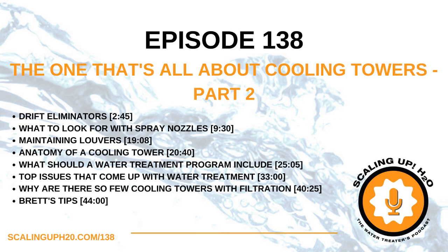So a couple other quick ones. These units, because they have the spray pump and the riser pipe on them, the closed circuit coolers and evaporative condensers, that is, with the coils inside, have a much smaller water volume. What that means is they are going to have a high water turnover rate, right? They're going to cycle up quicker and you're going to be bleeding water. So if you're going to be using a non-oxidizing biocide, you're going to need to use one with a faster kill.